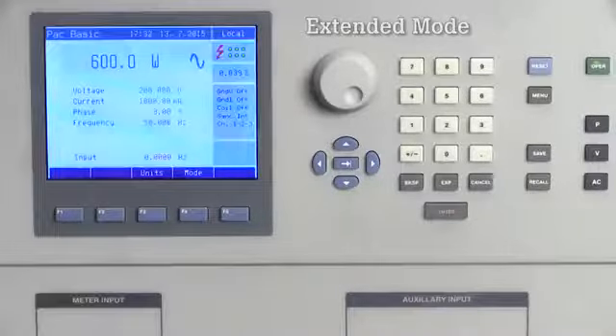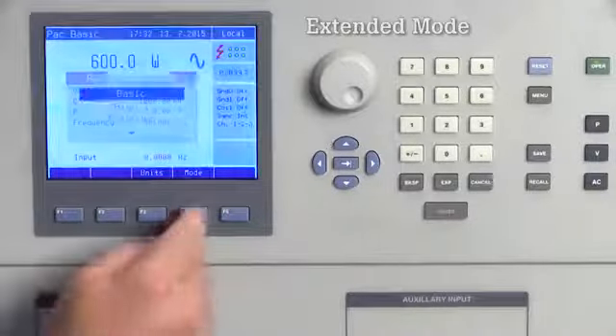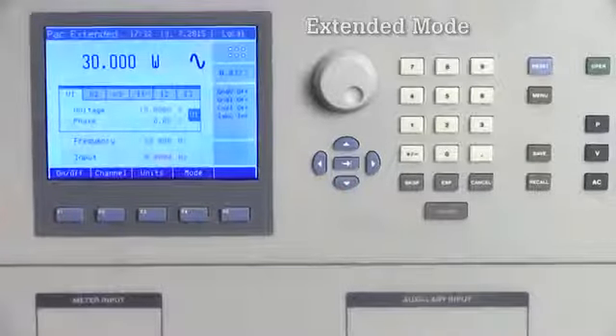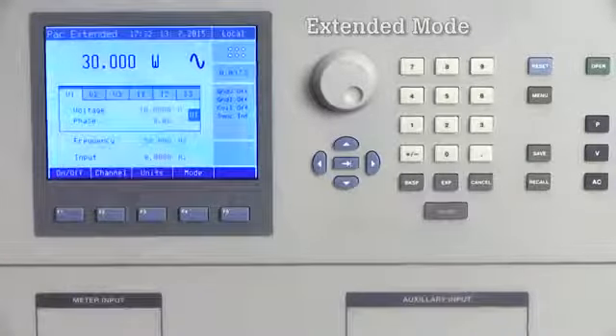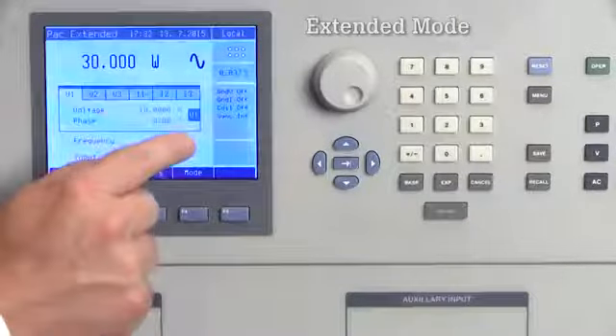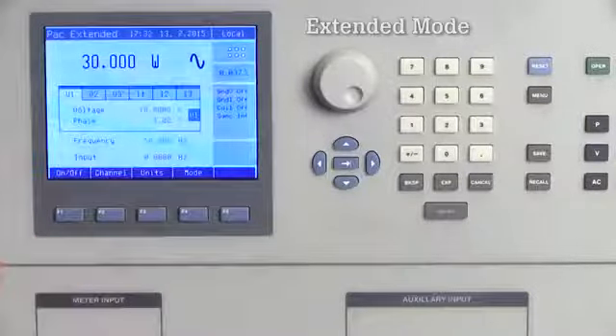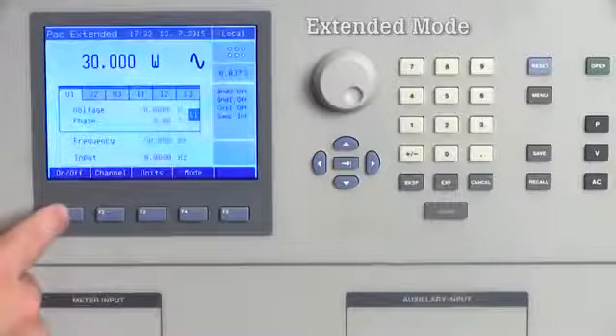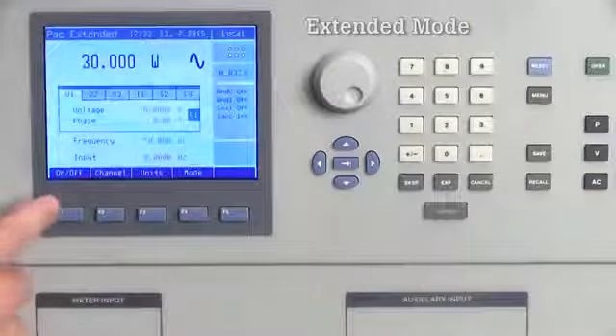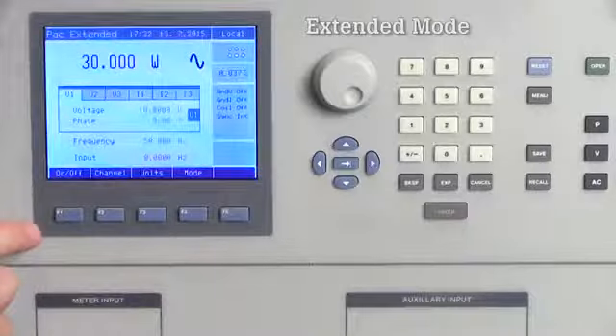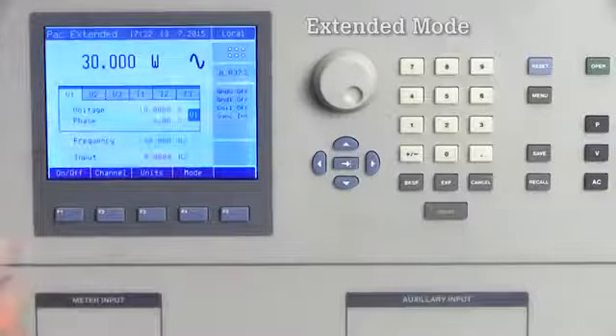For example, if you select the extended mode, you will be shown a menu that shows six channels, three voltage and three current. From here, you can toggle channels on and off with a push of a key. You can also change the values for each channel without affecting the others.